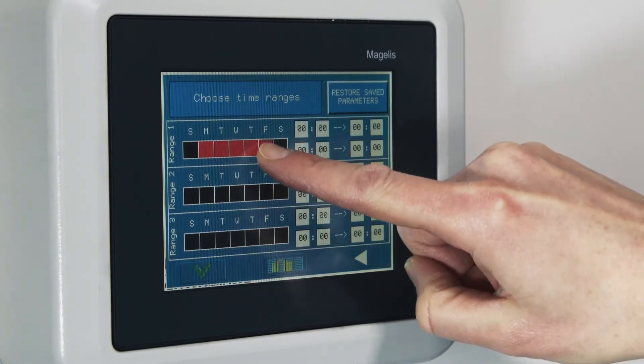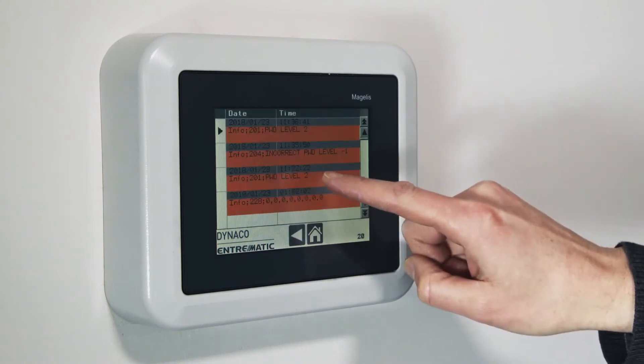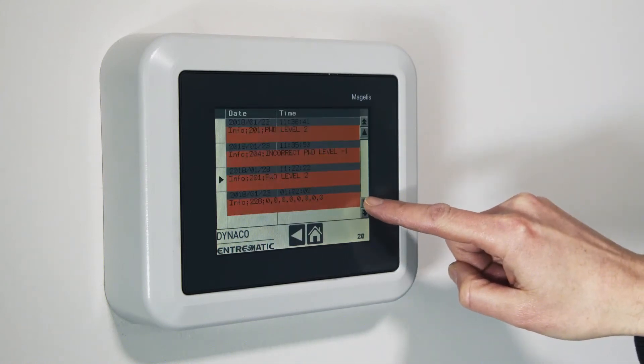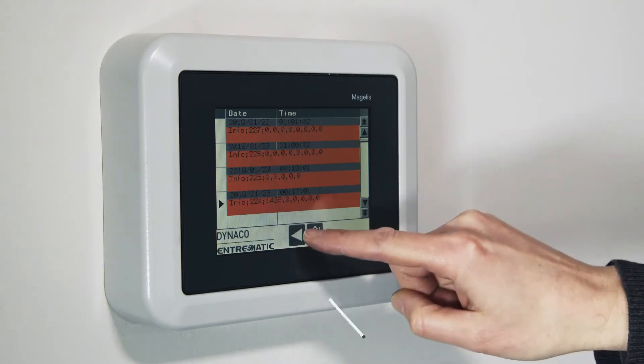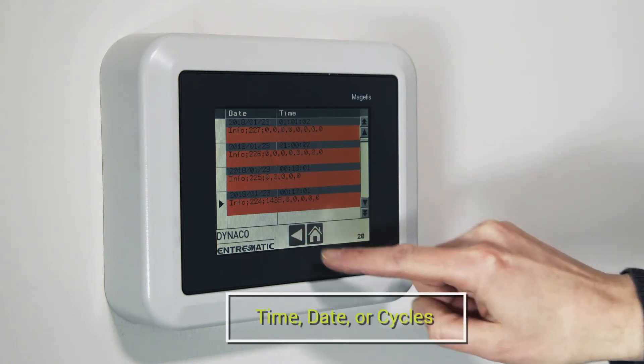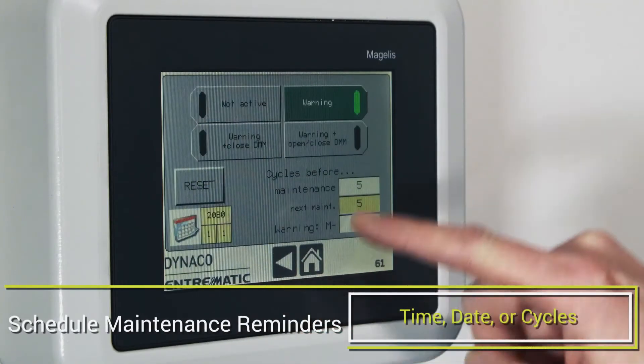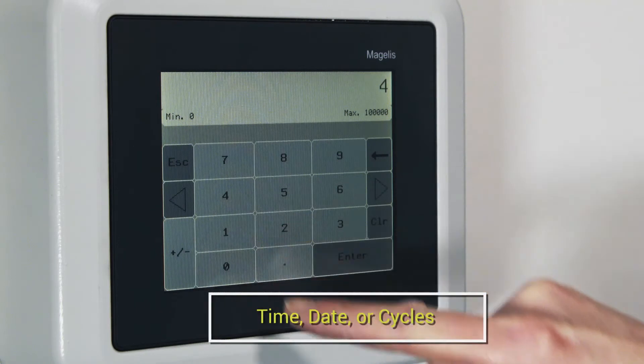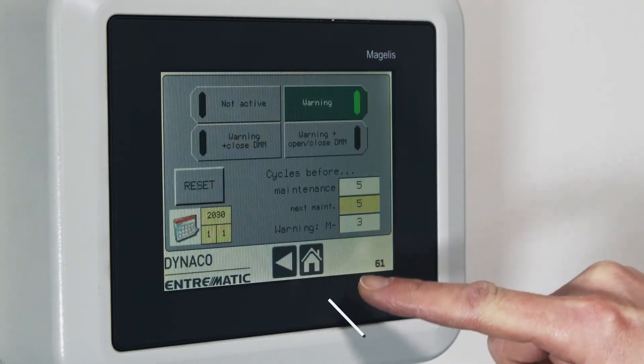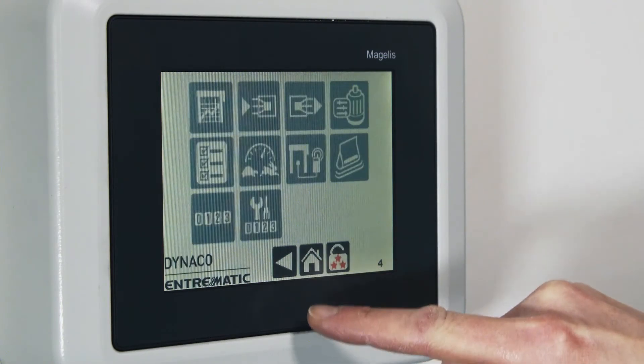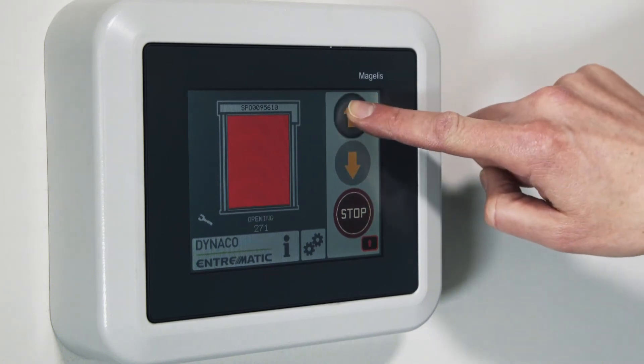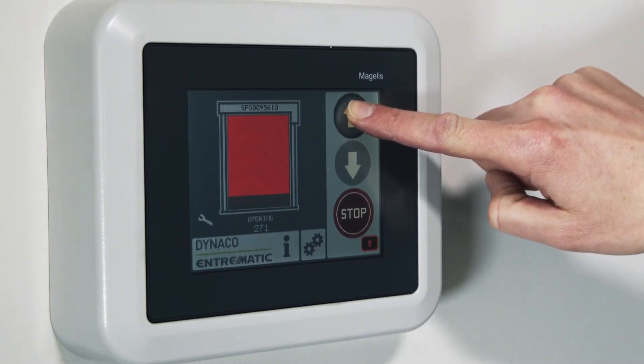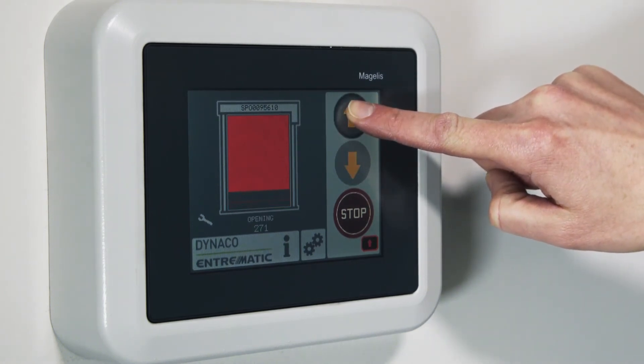Service technicians can view logs and error codes without ever having to open the control box. Most importantly, they can schedule periodic maintenance reminders based on time, date, or cycles. When the door is due for maintenance, the DynaLogix 5 will show a reminder. If the scheduled maintenance date has passed without service, the door can be set to run in dead man mode, requiring human interaction.